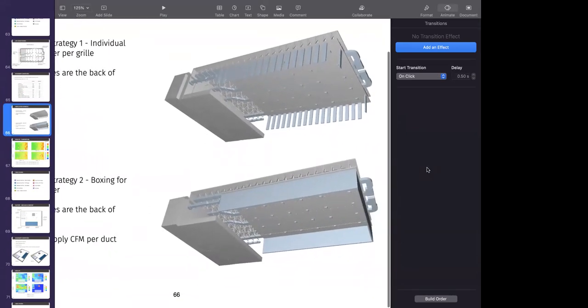So if you see, what had happened was there are only 2 return air risers at the back of the hall, and there were individual return air risers on the side. In strategy 2, the boxing was provided simply for aesthetics sake, to be very honest. But what was later done, the return risers at the back, considering there were only 2 of them, were increased to 5, and equidistantly placed so that we can get a more uniform extraction of heat at the back of the hall.